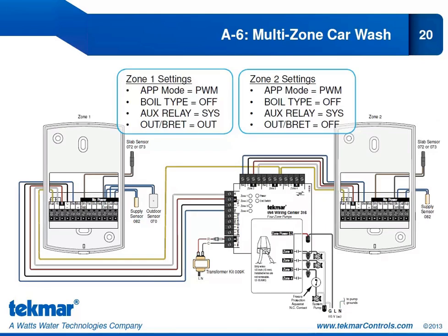And here we have the wiring for this application. Zone 1 654 is connected into the Zone 1 input on the 316. Likewise, we have Zone 2 connected into the Zone 2 input on the 316. Now let's follow these wires. We have R, C, and TN4 from the 316 coming into R, C, and TN4 on the 654. We're using our heat relay for the W call on the 316.